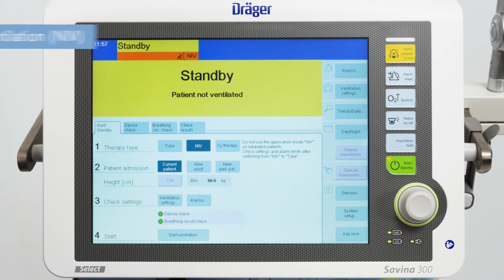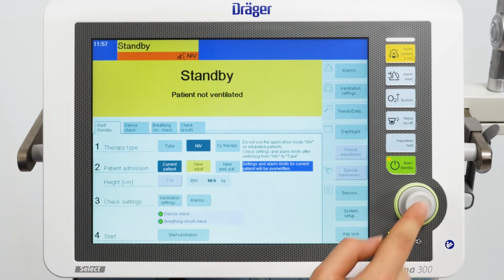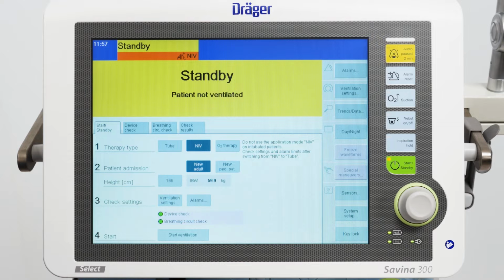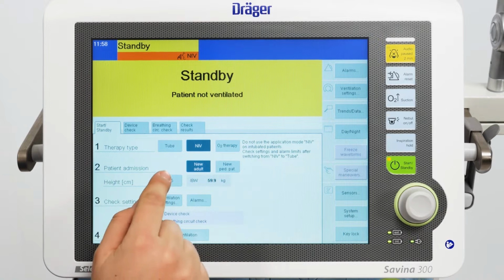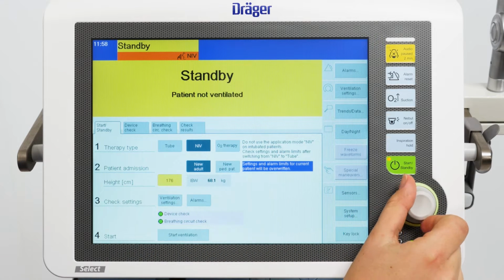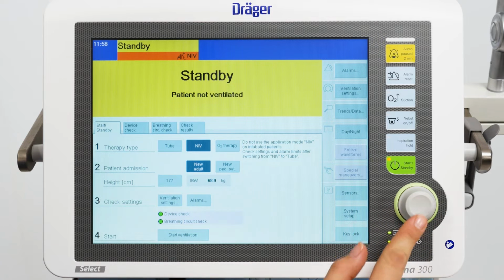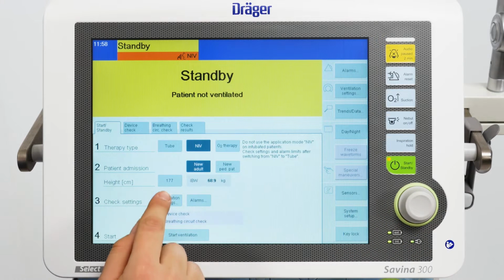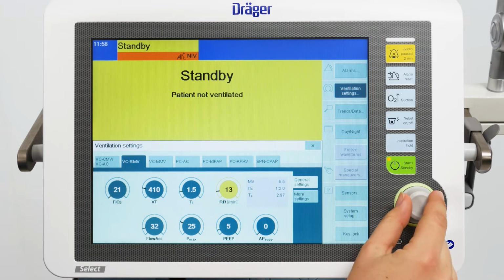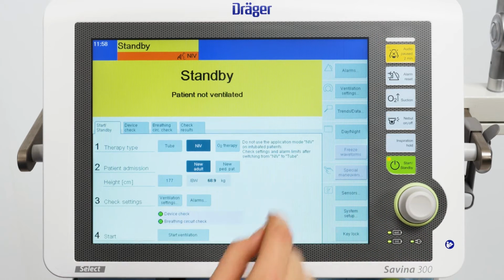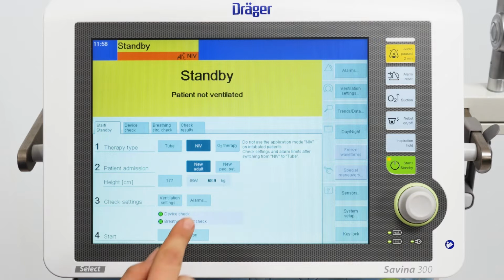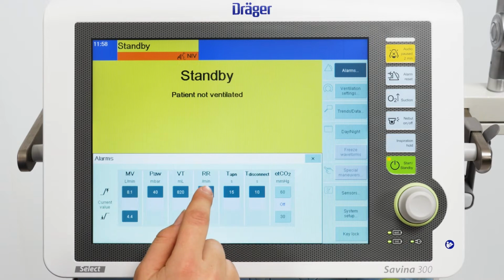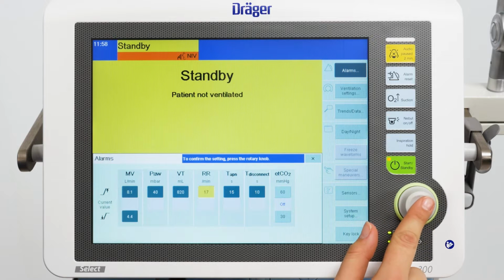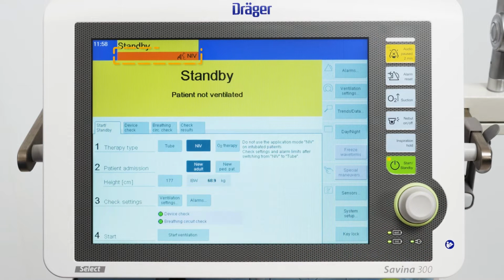Now select between current patient, new adult, or new pediatric patient. When you select a new patient, type in the body height. The ideal body weight is calculated by the body height. Select the Ventilation Settings button and select the appropriate settings and confirm with the rotary knob. In the application mode NIV, all ventilation modes can be selected. Then select the Alarms button and set the alarm limit accordingly and confirm with the rotary knob. In application mode NIV, the symbol is displayed in an orange area in the header bar.